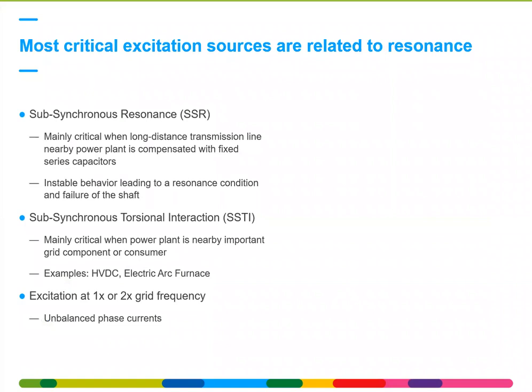So the most important, well-known examples are subsynchronous resonance, where these are critical when you have long-distance transmission lines which are compensated by fixed series capacitors. This can lead to unstable behavior. More details further on. Subsynchronous torsional interaction as well, for instance, with HVDC stations, electric arc furnaces, damage has already occurred in the past. And the third one is excitation at once or twice grid frequency. So these are related to unstable regimes, resonance, where you excite the mechanical shaft line up to torsional vibration amplitudes which are damaging the machine.